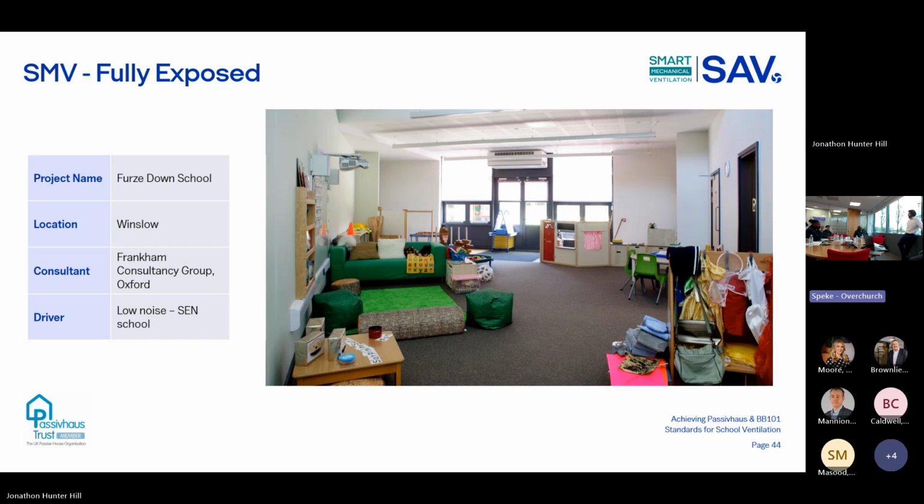It's normally pretty quick. So one of the big benefits of Airmaster is a quick installation, and there's no real commissioning process because if we just have a connection through a wall, 300 millimeters, say, there's no pressure drop to speak of except for what the grill has. So the fans, the throughput that we claim on our data sheets is very easily achievable. The data sheet condition is almost always the same as the installation condition.